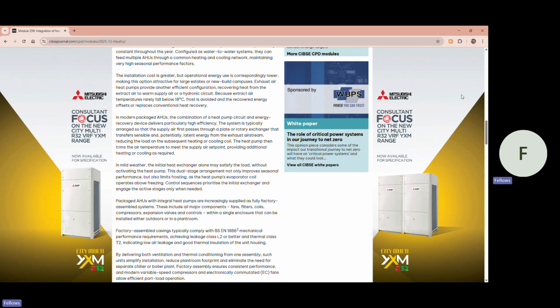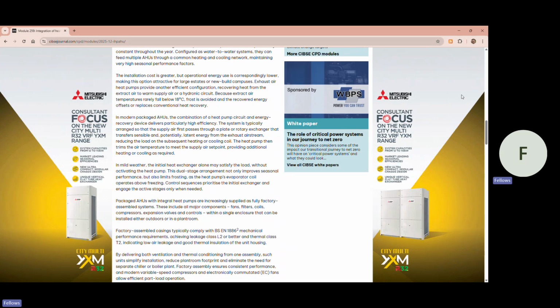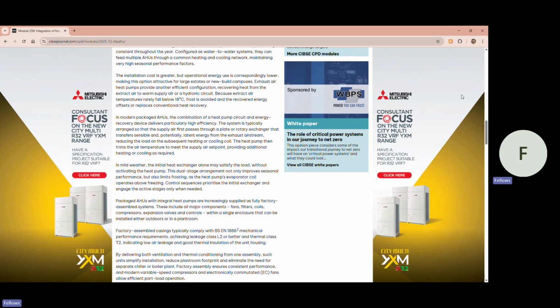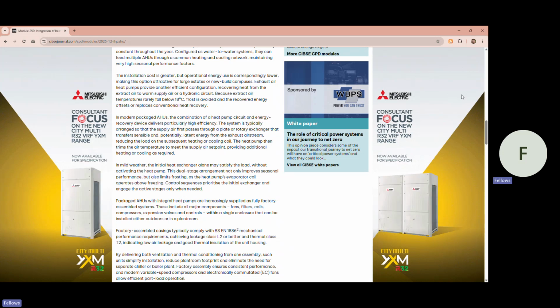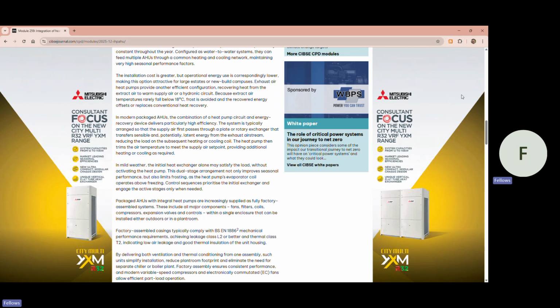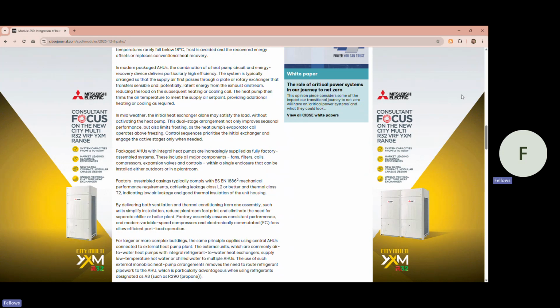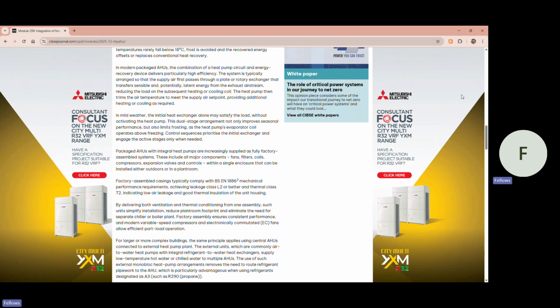This dual-stage arrangement not only improves seasonal performance, but also limits frosting as the heat pump's evaporator coil operates above freezing. Control sequences prioritize the initial exchanger and engage the active stages only when needed. Packaged AHUs with integral heat pumps are increasingly supplied as fully factory-assembled systems.